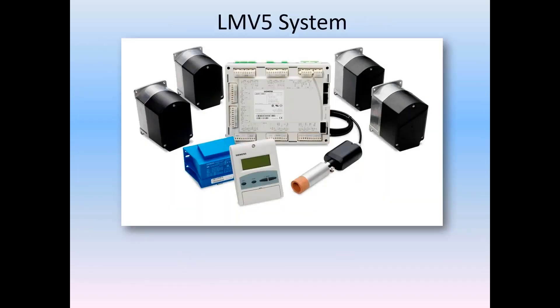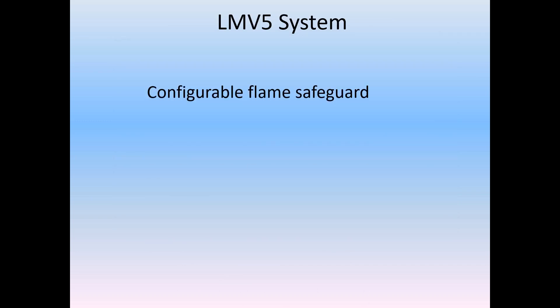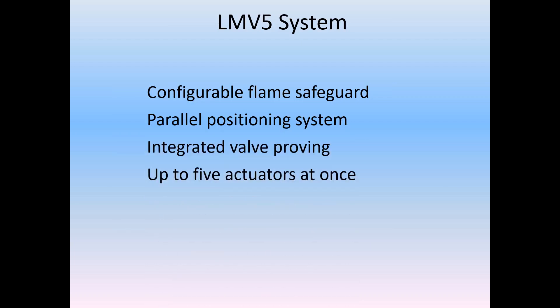The LMV5 system, shown here, has primary features that include a highly configurable flame safeguard, a parallel positioning system for fuel-air ratio control and integrated valve proving, and up to five actuators working at once for fuel, air, an internal PID controller, as well as optional O2 trim and variable frequency drive control.